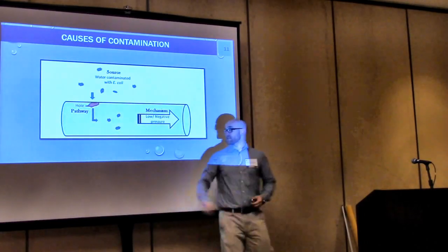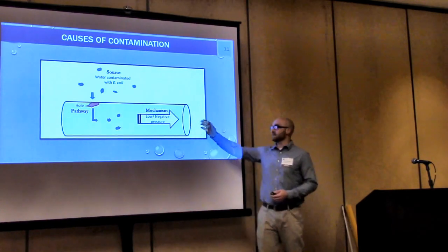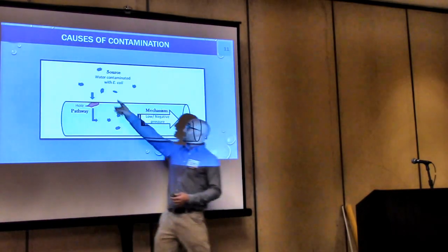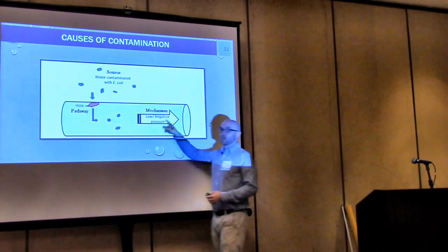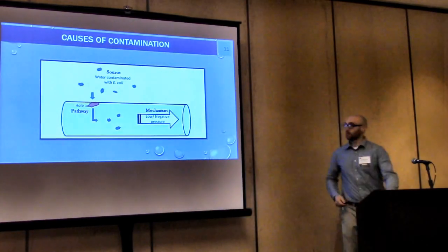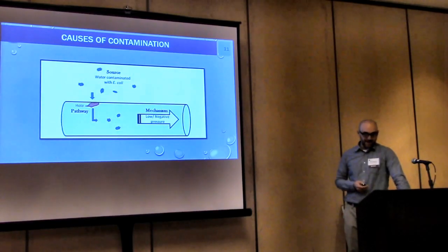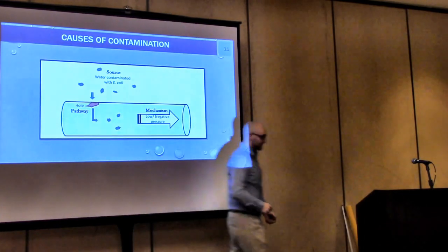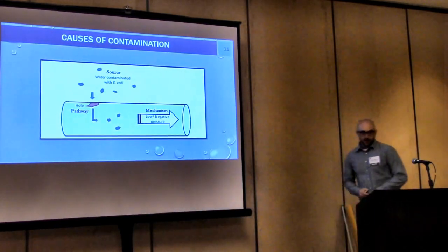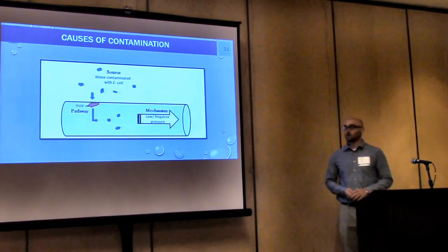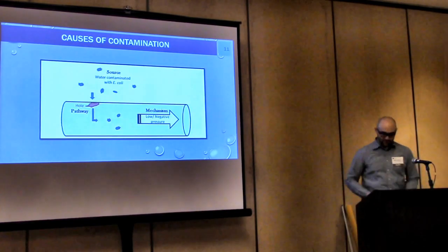Normal operations, right? Water's going to go that way until something down here happens: a leak, flushing, some sort of maintenance, things like that, causing lower or negative pressure. This contaminated water will then be brought into the system. So the RTCR requires systems to assess the pathways of contamination, tighten stuff up, fix holes, patch this, tighten that. It also helps you assess and reduce some of the mechanisms by which all this can happen.